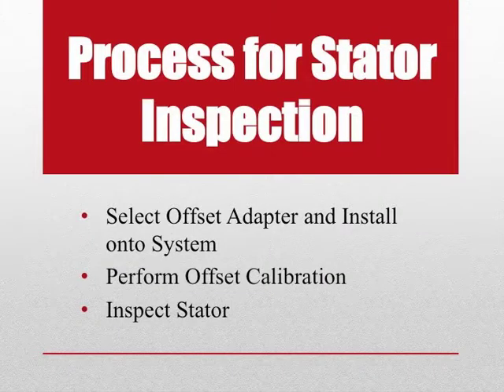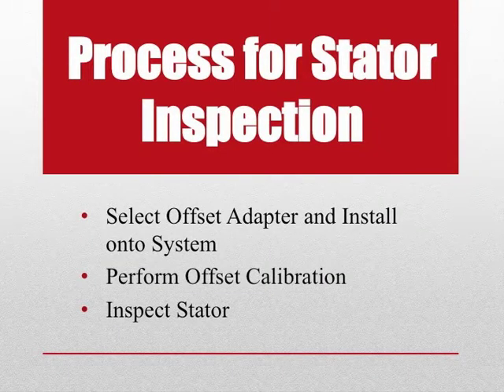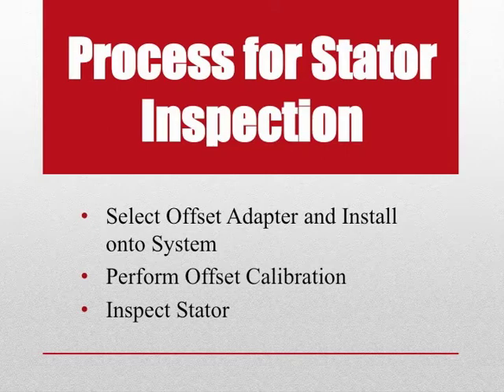The process for obtaining full profile data begins with choosing the corresponding offset adapter for the stator, performing the offset calibration, and then inspecting the stator itself.